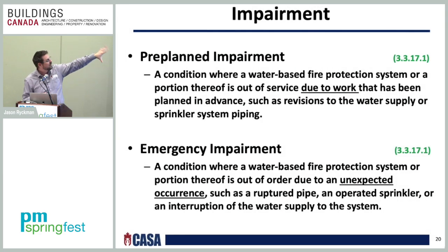With impairments, there are two different types, as I mentioned: pre-plan and emergency. A pre-plan impairment is a condition where the water-based fire protection system or portion thereof is out of service due to work. Ultimately, this has to be planned in advance, such as any revisions to the water supply or sprinkler system piping. Any system impairment can also lead to other dangers, as mentioned.